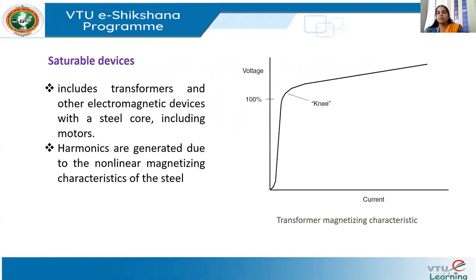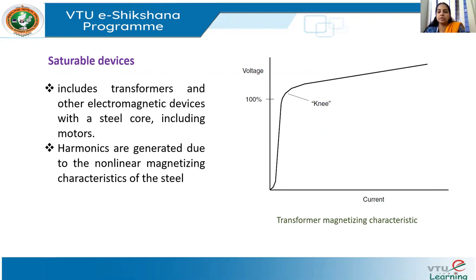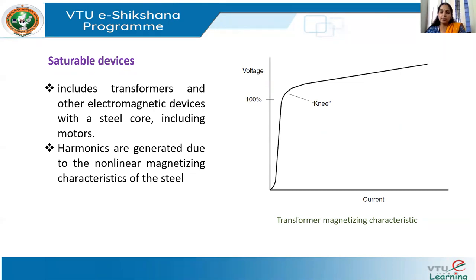Now let us come to saturable devices. Saturable devices are those where the magnetic core gets saturated. The most important and widely used saturable device in power systems is the transformer. Normally a transformer is a linear device, but when saturated, there is a knee point beyond which the relationship becomes non-linear. Saturable devices can therefore be considered non-linear devices when they enter saturation.